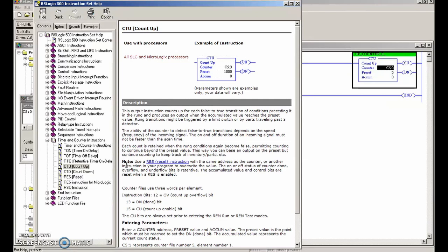It says in big bold letters: note - using a reset instruction with the same address as the counter or another instruction in your program will overwrite the accumulated value. The on or off status of the counter done, overflow, and underflow bits is retentive. The accumulated value and control bits are reset when the RES is enabled.